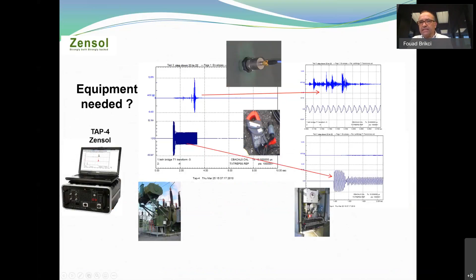What do we need to test? Here you can see the raw data. The vibration is picked up with an accelerometer, and the motor current with an AC or DC clamp. With this raw data, we calculate what we call the Hydro-Québec envelopes, a method patented by Hydro-Québec in 2001. Why do we use the envelopes? Because it simplifies the signal, gets the shape of the signal, and we focus only on variable impacts, easy to analyze, easy to compare.